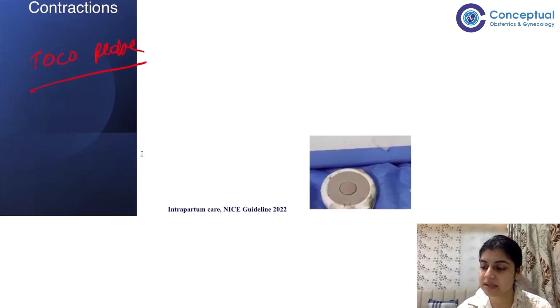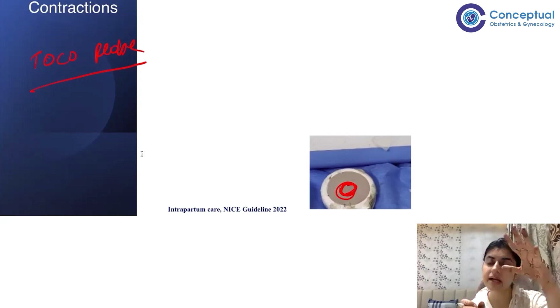The movement of the plunger is converted according to the contractions into an electric signal. The movements produce vibrations, which are converted into electric signals, and that is how you calculate the intensity of the contraction. It is not very sensitive in calculating the duration of each contraction. It tells intensity reasonably well. It also depends on how tight the belt is, so do not put a belt over the CTG probe. You should fix it gently with probe tape, or gently place it over the abdomen. You should not fix it so tight.